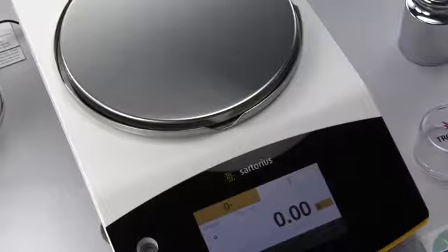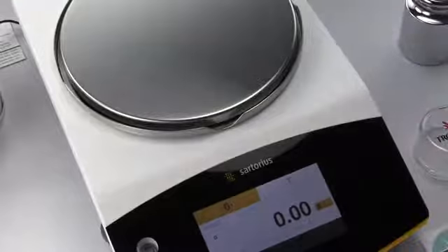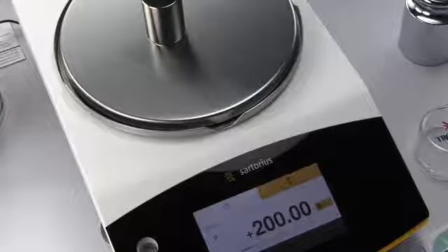We sell a lot of the Troemner weights, and you can also purchase something like a Troemner Cal Pack. And again, those are all optional accessories. Now, calibration weights, you do want to have them recalibrated annually by a third party. Probably Troemner, we would recommend, is the best in the industry, or that's who we have a relationship with. This is because the calibration masses over a period of time do have normal wear from fingerprints, scratches, even corrosion in the air that can contribute to changes.